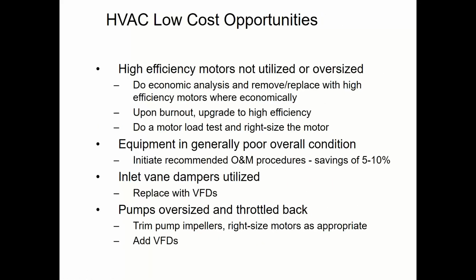Okay. All right, other things that we can do that are on the low cost side: changing out motors to higher efficiency motors. A lot of systems, especially smaller package systems, have low efficiency, 60% efficient PSC, permanent split capacitor style motors. Putting in a more efficient motor, perhaps a NEMA premium efficiency motor or an ECM motor if it's a relatively small motor, upgrading those motors can save us a bunch of energy.